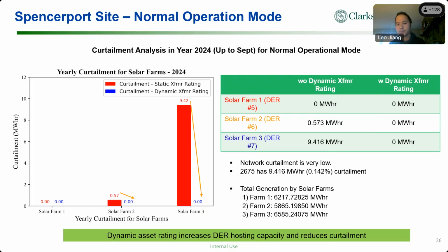There are multiple reasons that contribute to the low curtailment. I will not talk about all of them. For example, Zach talked about how originally the study used a 75% rating, but in the implementation they go to 80% or 85%. That is the controller setting that was implemented. So what this really says is that dynamic asset rating can increase the DER hosting capacity and reduce the curtailment in flexible interconnections. But this study is of dynamic asset rating in normal operational mode, meaning there is no communication outage or loss of communication. Now that's what I'm going to talk about next. Next slide, please.